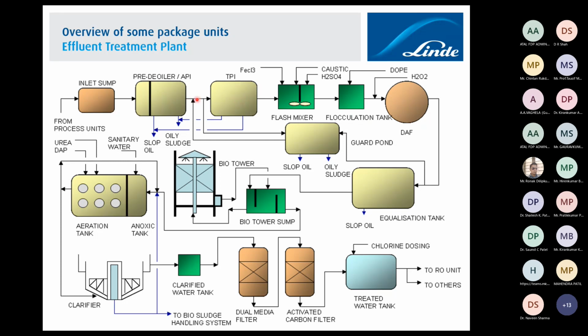So these two units basically remove free oil, and then you also have some emulsified oil which cannot be easily separated through a mechanical process. In that case, you have to inject some dewatering chemical like ferric chloride or some polymer, based on the dewatering nature. Once you do that, you also need some pH correction because it works at a certain pH only. So caustic and acid basically do the neutralization of the effluent.